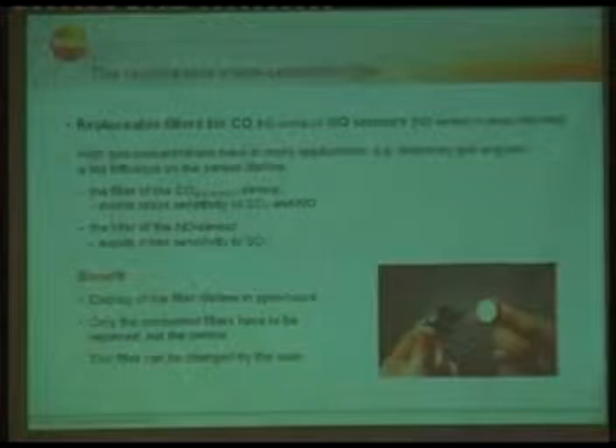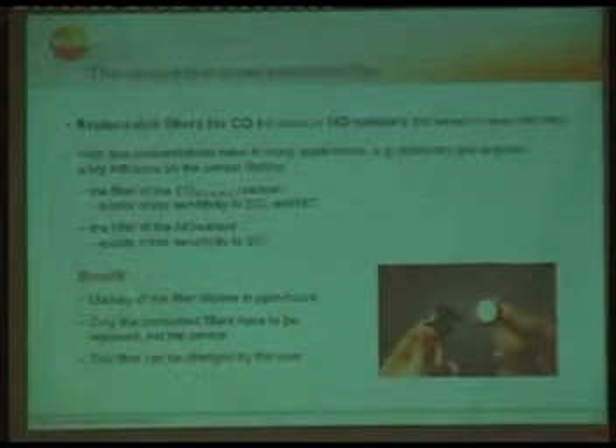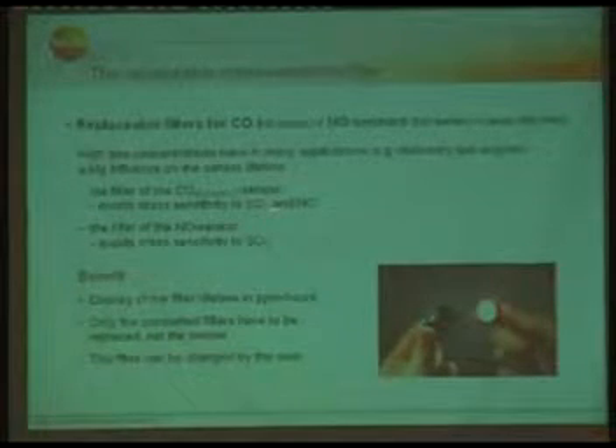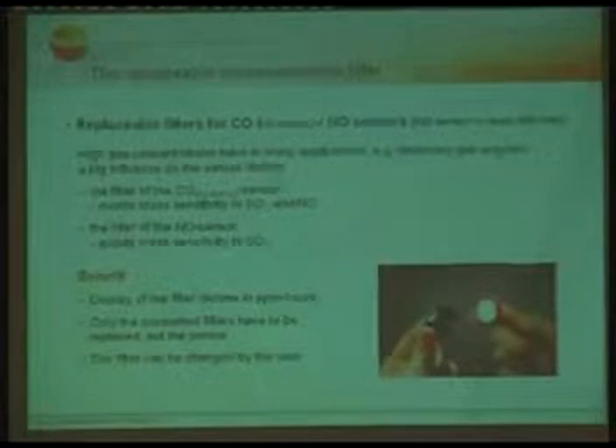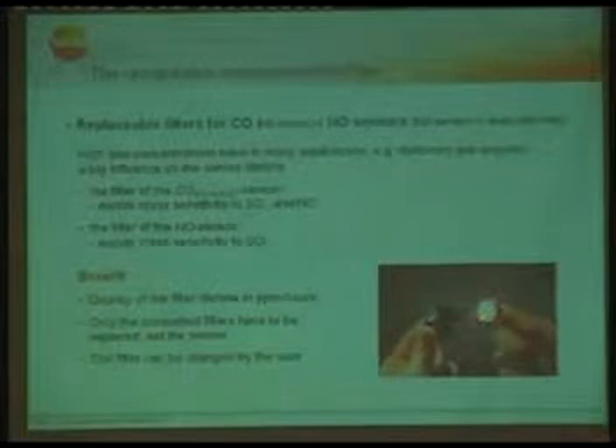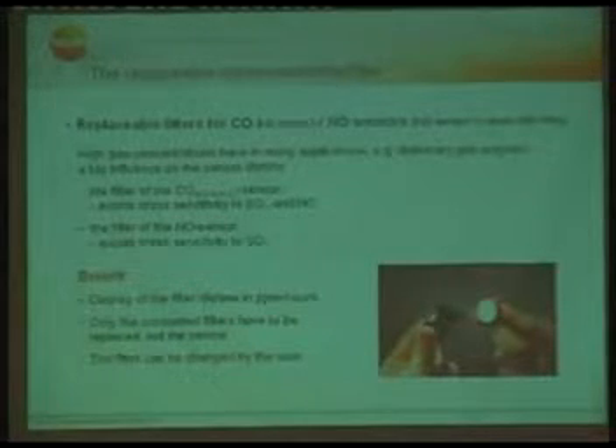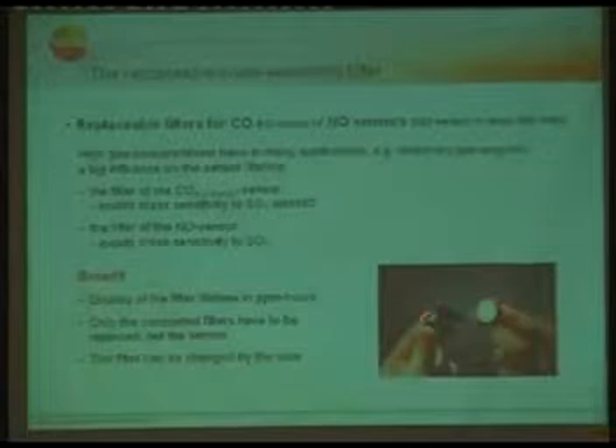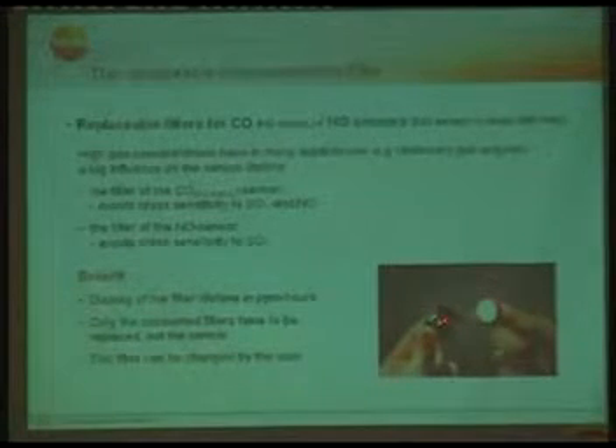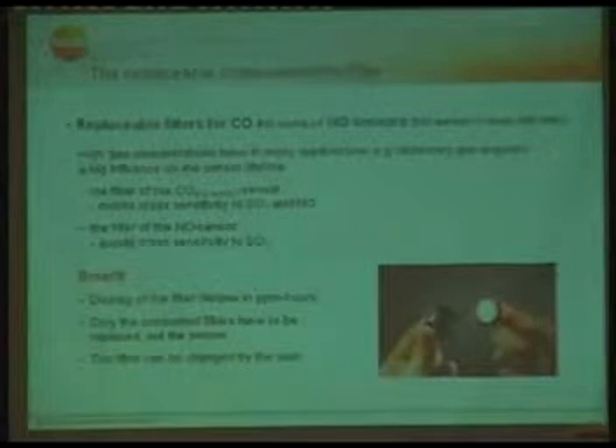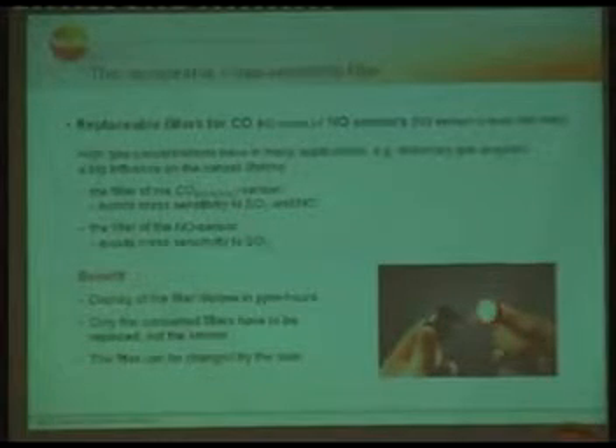And within the instrument, we have a so-called ppm counter. And depending on the concentration of SO2 and NO, it will calculate the lifetime of the replaceable filter. And then the instrument will tell you, oh, please change this filter, otherwise you will have a cross-sensitivity and it cannot be compensated anymore. But the advantage is, in the past, this filter was built in the sensor, and you could figure out if the sensor is still good or not with calibration gas. That means you had to put SO2 gas to the CO sensor, and then you could see if it reacts. Okay, the sensor is no more good. You have to change the whole sensor, which was expensive.